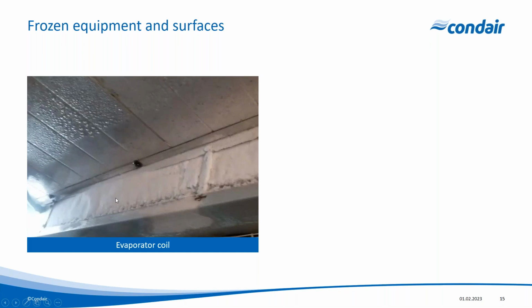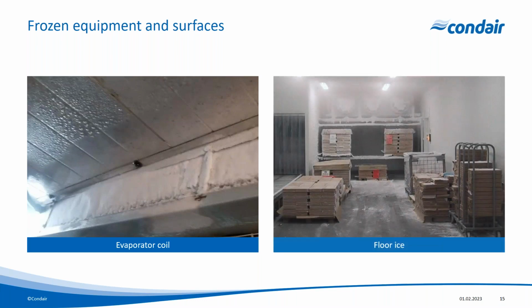And you can see that the coil is a solid block of ice, as we've got air ingress into the cold store, and air is being circulated over the evaporator at a high rate. And of course we've got that accumulation of ice in the evaporator. And this picture tells pretty much the story of all of those conditions.